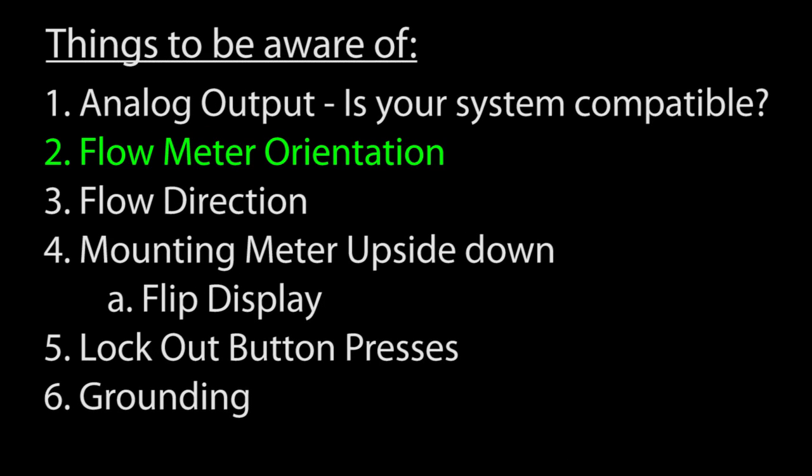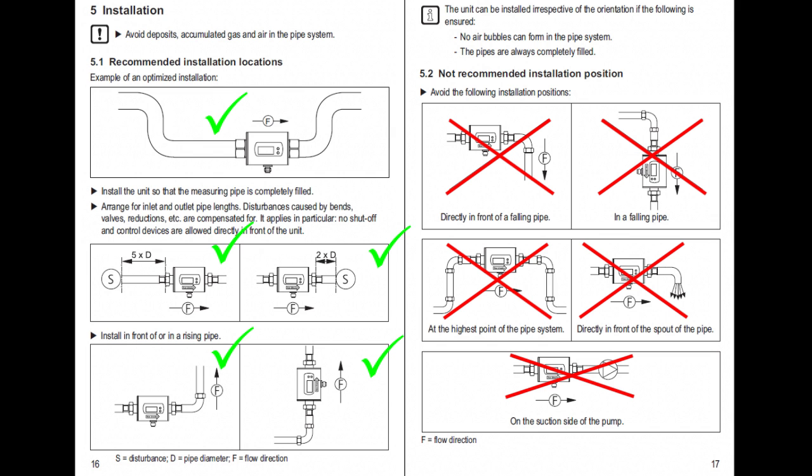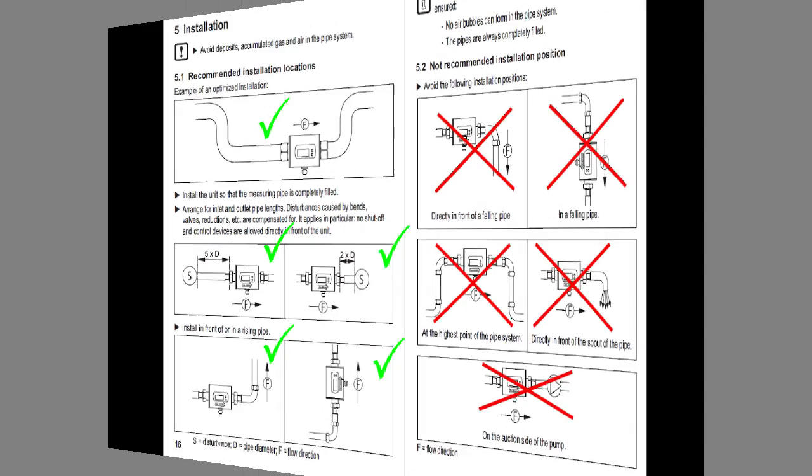The orientation of the flow meter is very important. There are a bunch of diagrams in the user manual that show you the proper orientation, but the bottom line is you want to install the flow meter so that it never gets any air bubbles stuck in it. You want a solid stream of liquid to get accurate results.